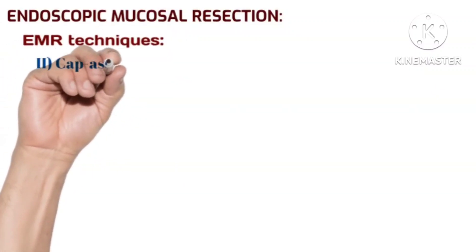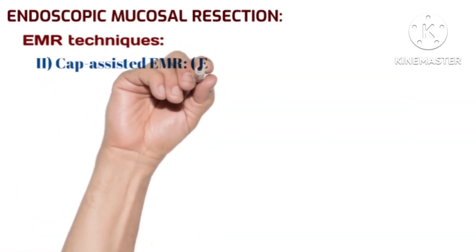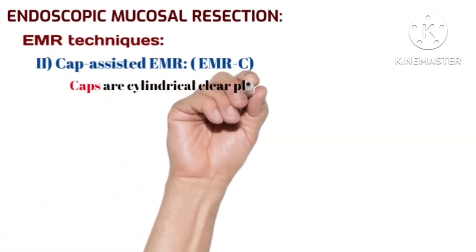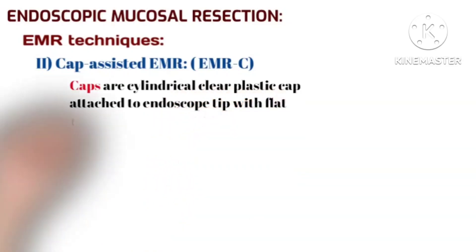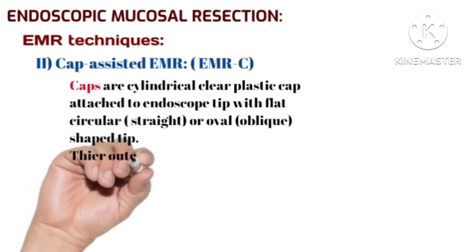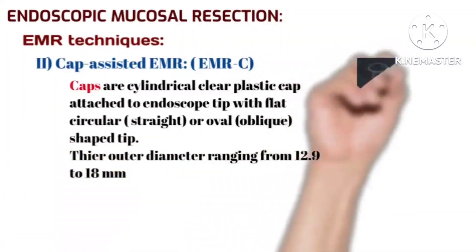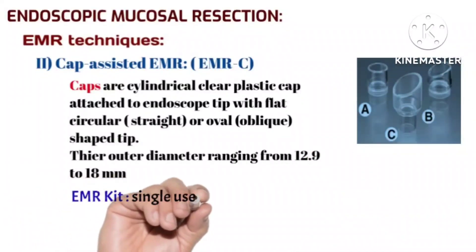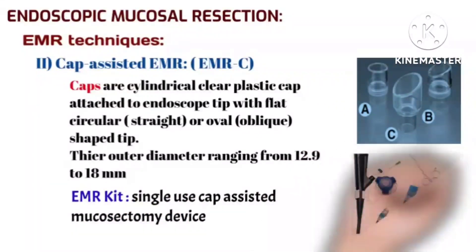Caps are cylindrical clear plastic caps attached to the endoscope tip, with either a flat circular straight end or an oval oblique-shaped tip. Their outer diameter ranges from 12.9 to 18 mm, as shown in the first image. The second image shows the endoscopic mucosal resection kit, which includes a single-use cap-assisted mucosectomy device.